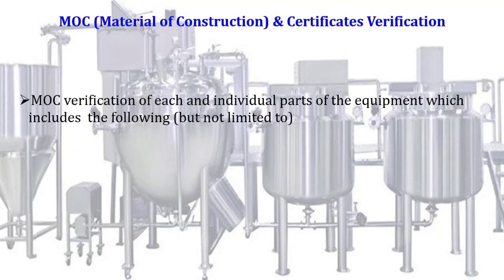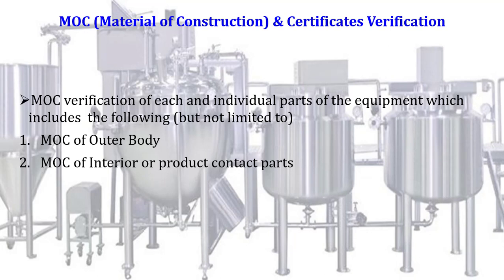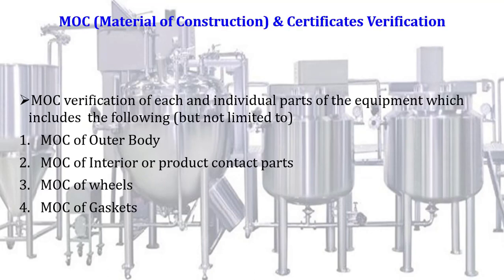The next stage is MOC — material of construction — and certificates verification. In this stage we verify the material of construction of each and individual part of the equipment, including but not limited to: MOC of outer body, MOC of interior or product contact parts, MOC of wheels, and MOC of gaskets. In other equipments, MOCs of additional parts are also included.